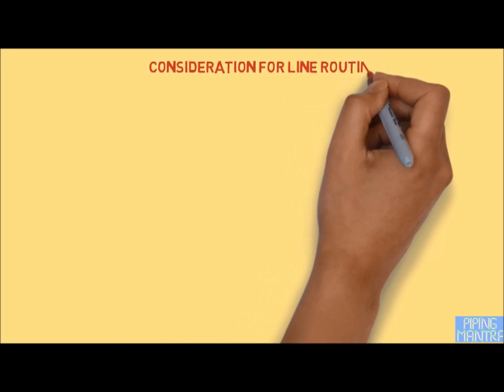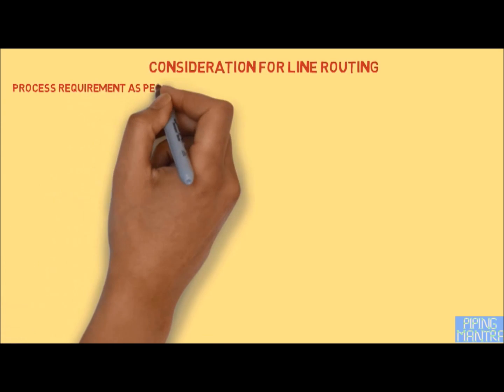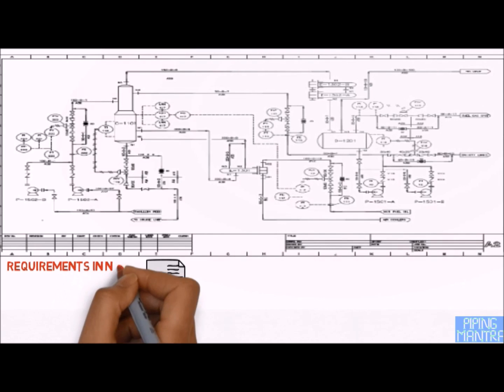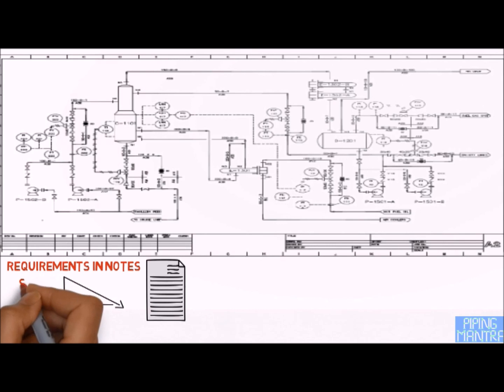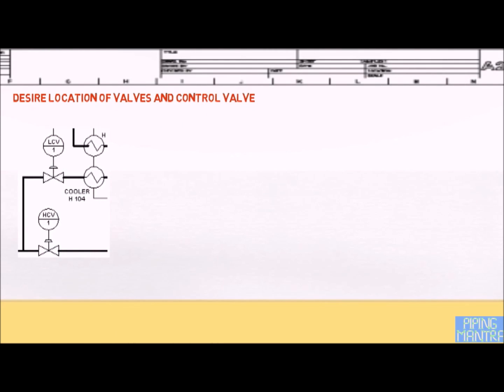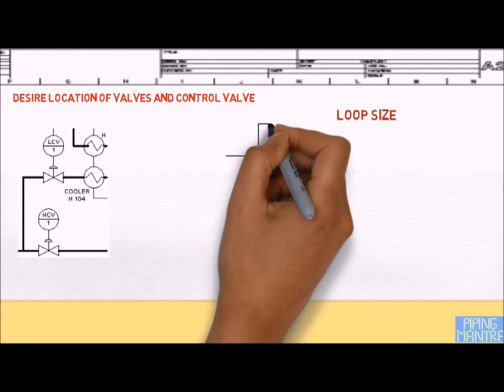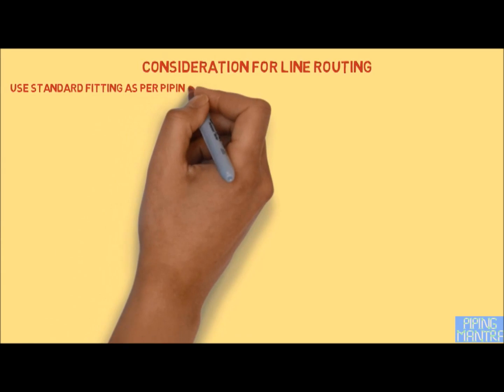Now we will cover the procedure for line routing. The basic requirement is that it should meet the process requirements mentioned in the P&ID. We also have to refer to written notes in the P&ID for specific requirements such as slope, loop size, length of barometric legs, restriction of piping length on horizontal or vertical legs, and desired location of valves and controls. We should use standard fittings as per the piping material specification.